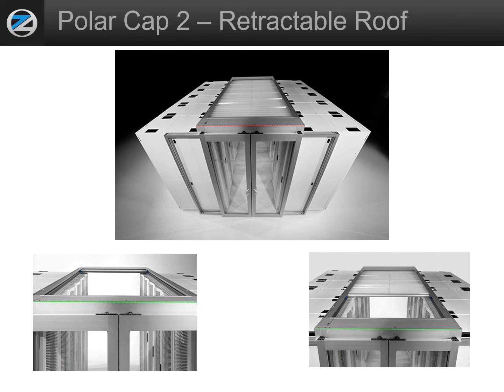Or you can go with the Polar Cap 2. This patented product is the first fully NFPA compliant containment roof system. It attaches to the top of racks and forms a ceiling that prevents hot and cold air from mixing. It is fully electric and retracts into a metal housing when the fire suppression system is alarmed, so a pre-action system that reacts to a smoke detector ensures the containment roof is fully retracted long before the fire suppression system discharges. The Polar Cap 2 can also be opened and closed manually when maintenance is required above the containment space.